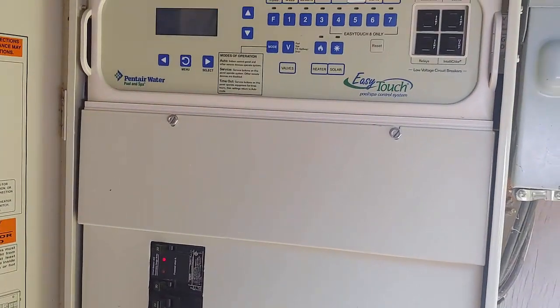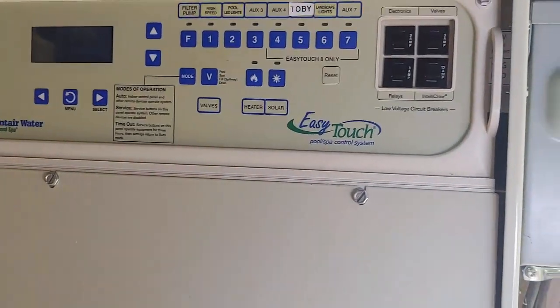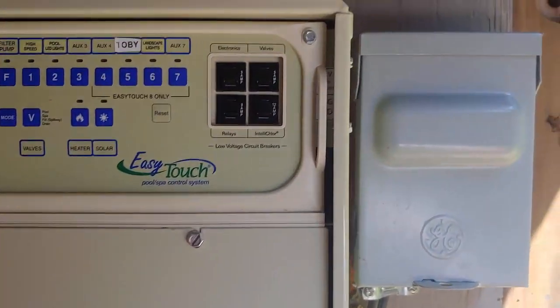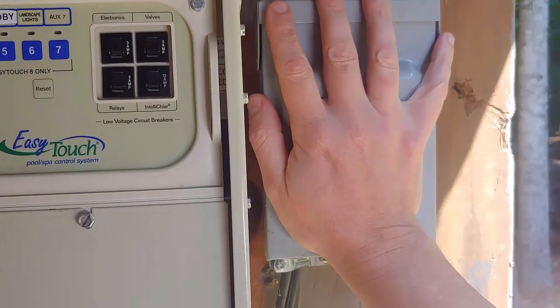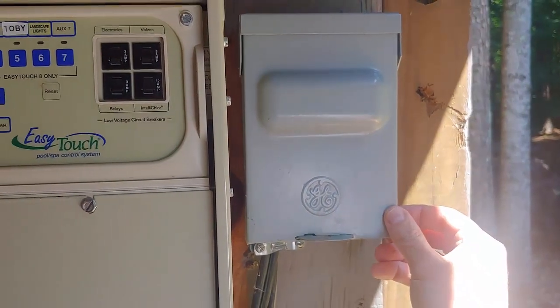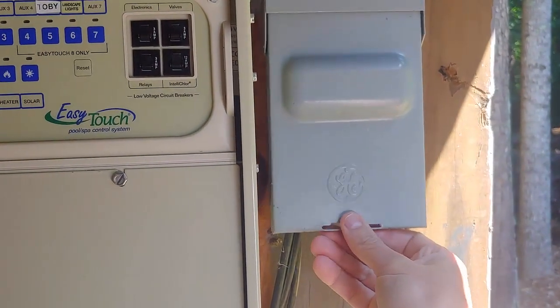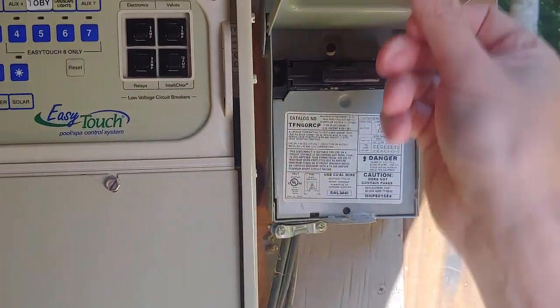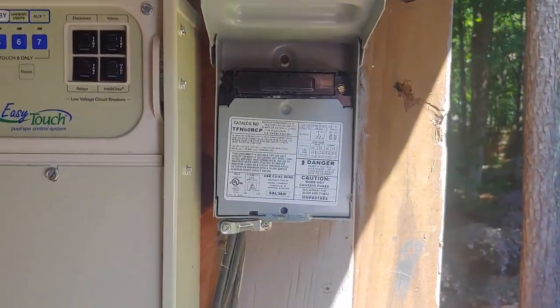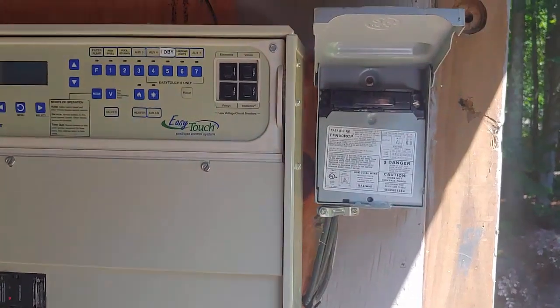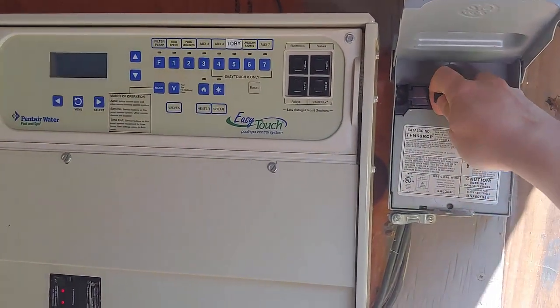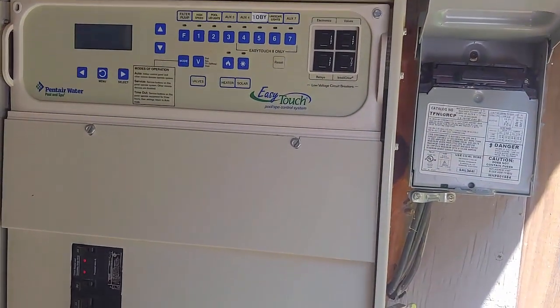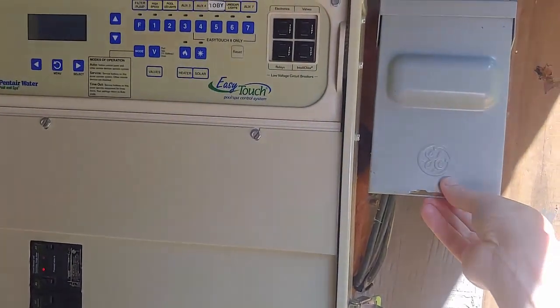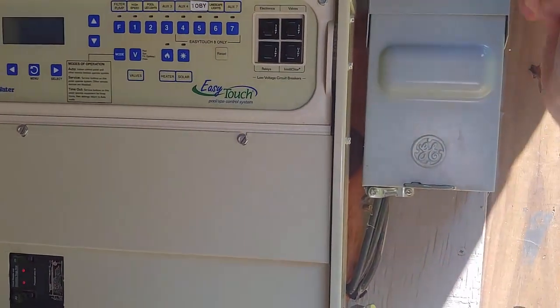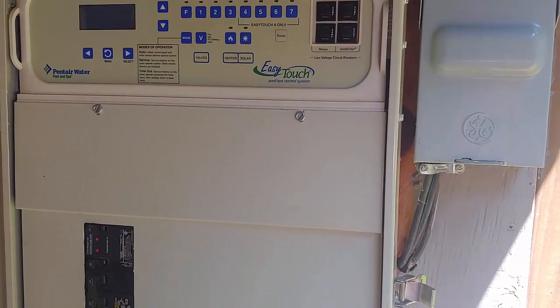When you are installing this, some of the general concepts to keep in mind is it's really good for you to have a cutoff switch out here. This is one of the more affordable cutoff switches, the same one you'd use for an air conditioner, 240 volts rated. To cut off everything, you simply pull this plug out and it cuts the main off. You can also get different versions of a cutoff switch that have an actual switch or a giant breaker.